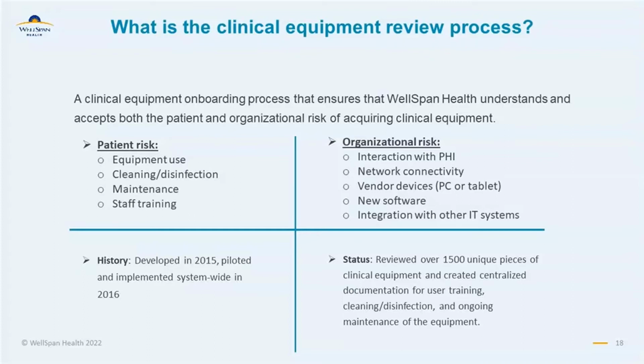Avoiding patient risk also involves understanding how equipment should be cleaned or disinfected. This is the key factor in avoiding patient harm. We collect manufacturer user manuals and cleaning and disinfection instructions. Those are thoroughly reviewed and understood, and there are some different ways that we use this information. So let's just say that there's a piece of equipment that has a wipe down protocol. So we ensure that the user understands what chemicals are approved for use on the device. That might not seem like a very important thing, but if you understand that the wrong chemical can affect the long-term functionality of the equipment and increase the likelihood of patient harm, and can even void a manufacturer's warranty, then you start to see the importance of considering this information.